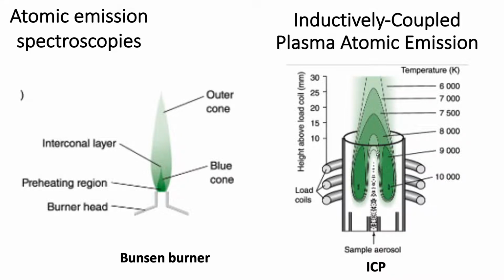So you're introducing this spray, and then on the outside here, you're introducing a lot of argon gas, right? An inert gas is not going to get too involved in this, and the spectrum from argon is not going to be interfering in the visible or where you're looking. But the flame that you get here comes from the fact that this coil is connected to an RF, radio frequency power source, and you're pumping power into this thing, like kilowatts of power, enough that you break down, you cause a plasma to form, like you have in a fluorescent light.